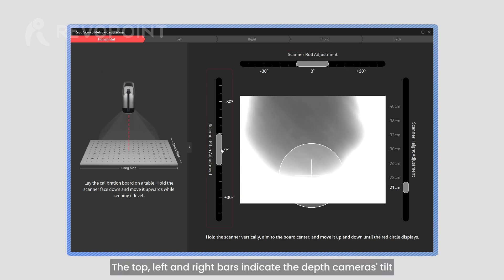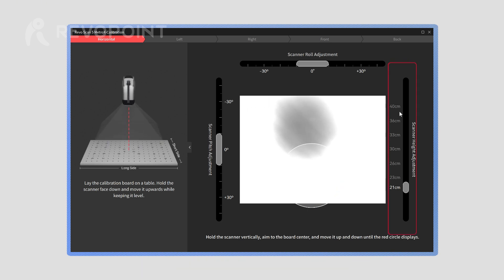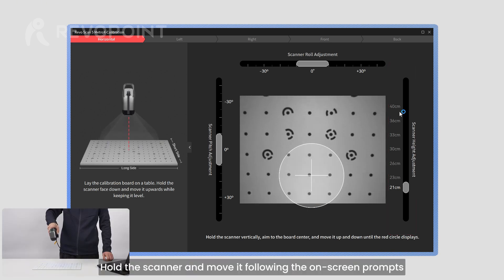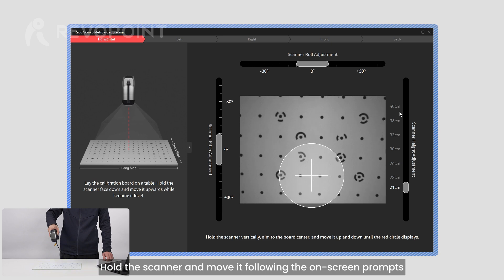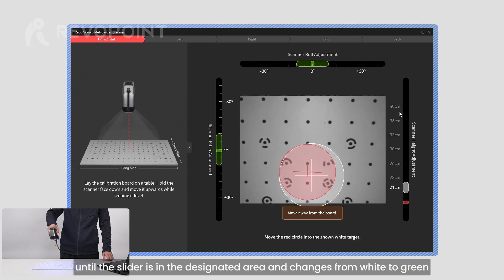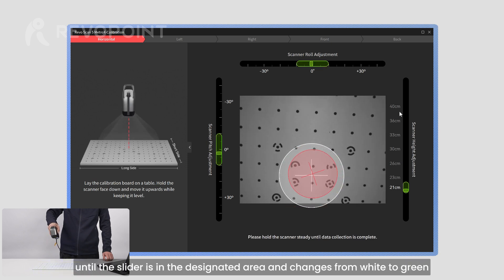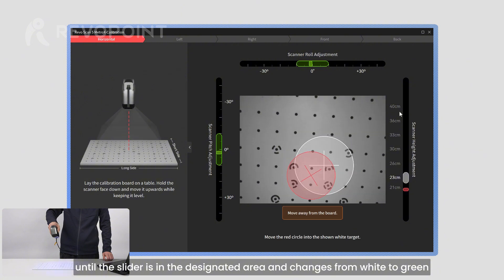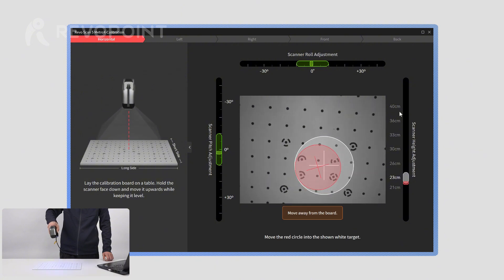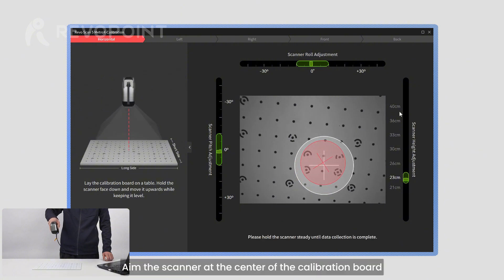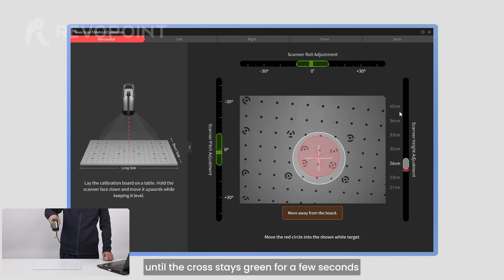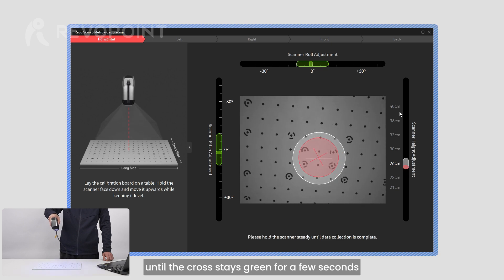The top, left, and right bars indicate the depth camera's tilt, pitch, and height, respectively. Hold the scanner and move it following the on-screen prompts until the slider is in the designated area and changes from white to green. Aim the scanner at the center of the calibration board until the cross stays green for a few seconds.